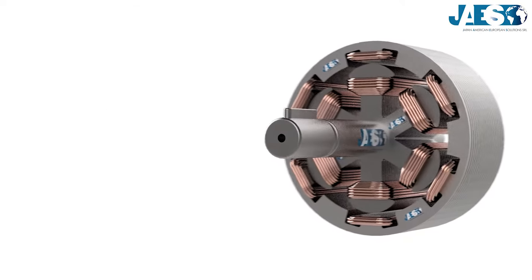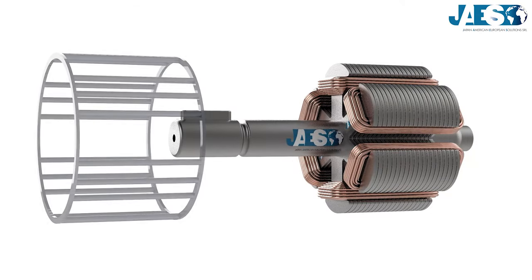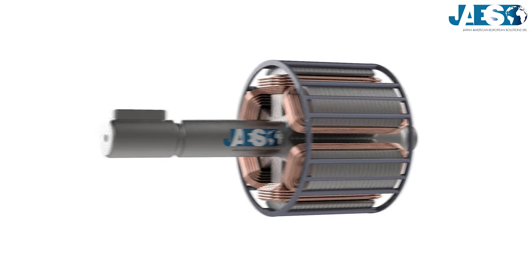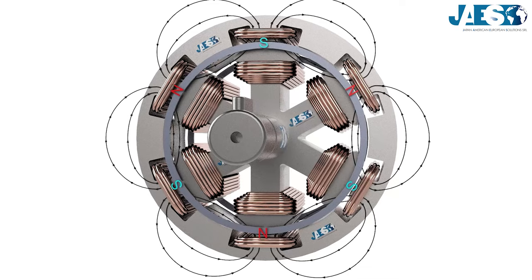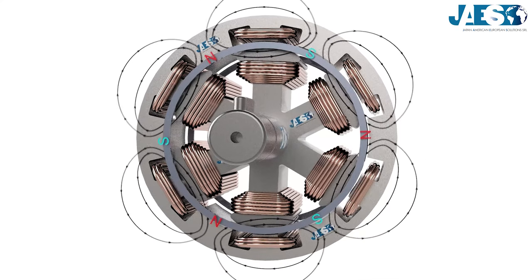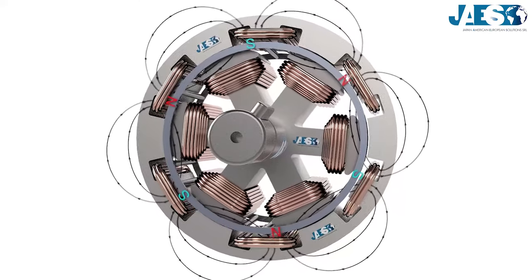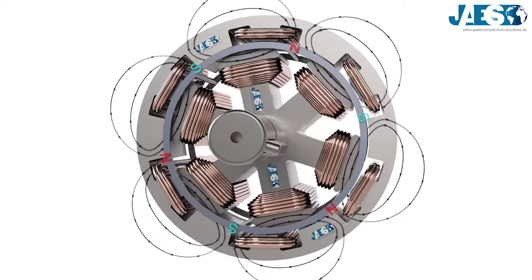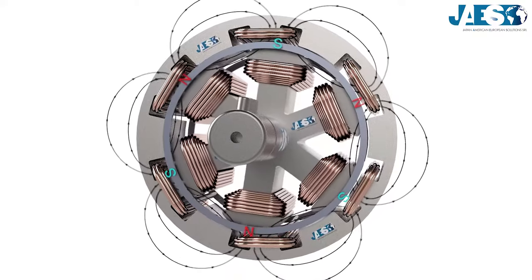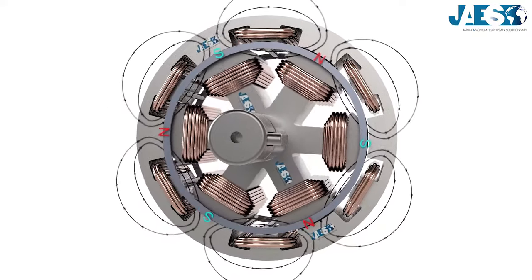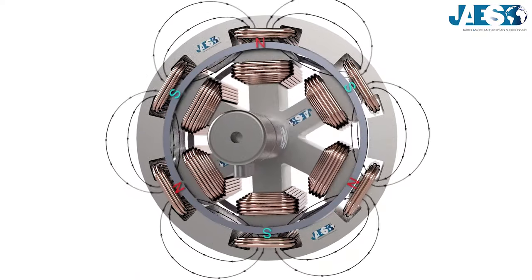In order to overcome these problems and improve the motor, a squirrel cage was introduced above the rotor coils. During the starting phase, the rotor coils are not energized. Therefore, the rotating magnetic field induces electricity into the squirrel cage bars, as in an induction motor. Once the synchronous speed is reached, the rotor coils are energized and start working again as a synchronous motor.